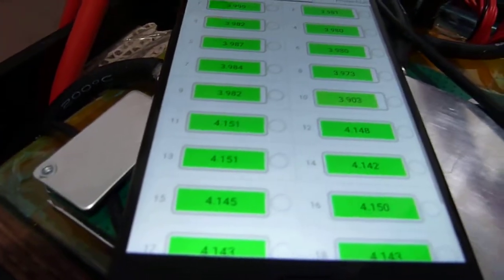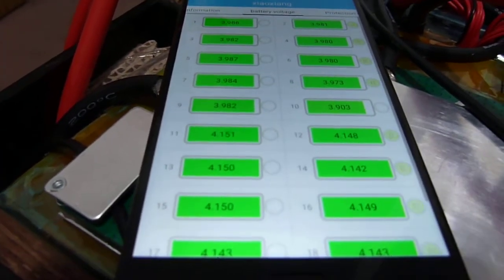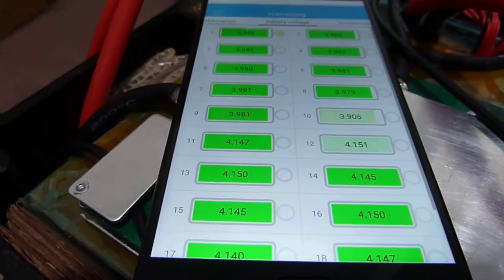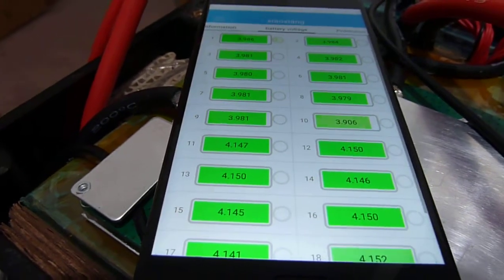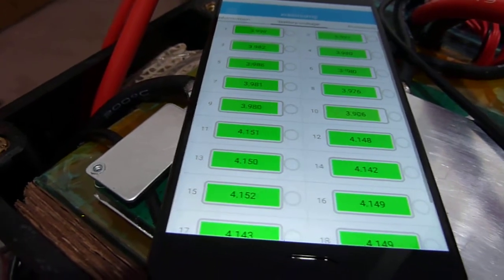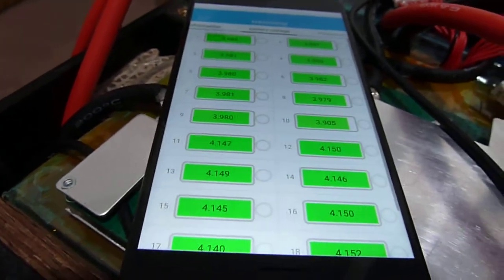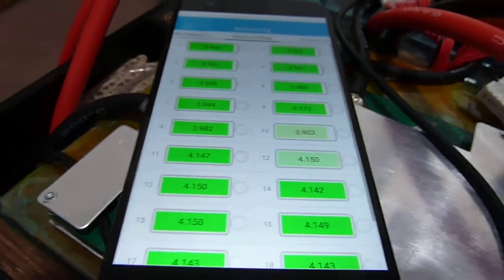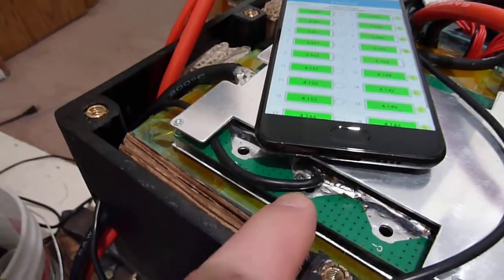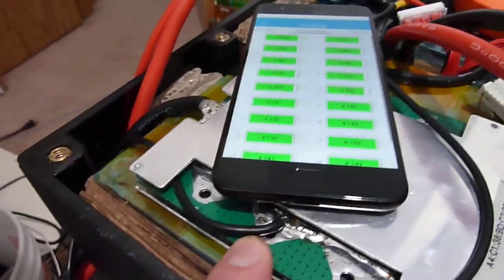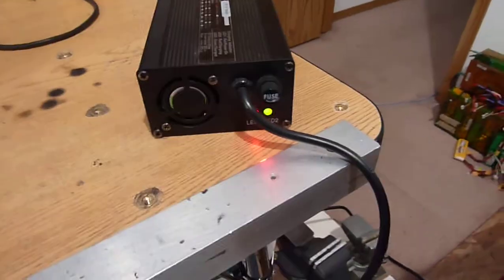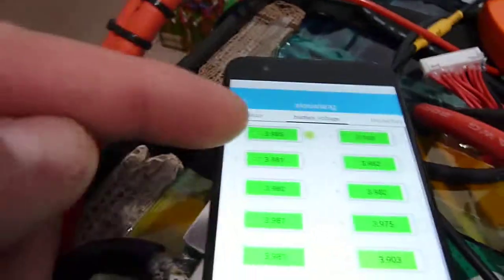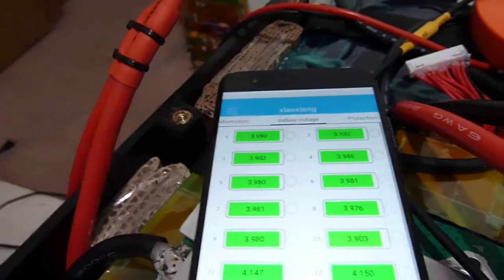So here is what happens. Those cells down at the bottom, 11 through 20, according to the settings I've got in the BMS, will balance down to 4.15 volts, which I have set in the parameter setting page. When that happens, the BMS, through its C- connection for charging, will turn on those MOSFETs and allow the charger to push current into the battery pack. That is to bring cells 1 through 10 up to voltage, and it's going to take a little while for this to happen and finally get done.